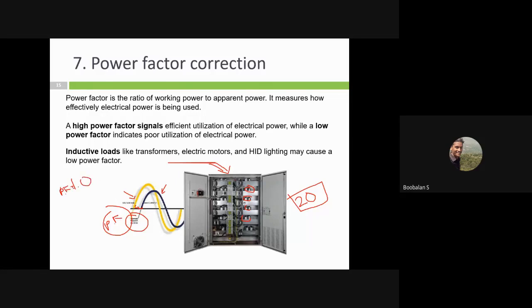It shows that my voltage waveform and current waveform are both in phase. Whenever we are connecting induction loads to the AC power supply, there is a lag between voltage waveform and current waveform. If you're using a capacitive load, there is a leading power factor occurring in my power supply. So inductive and capacitive loads lead to a power factor issue, causing low or higher power utilization in my electrical system. So power factor is a most important thing.